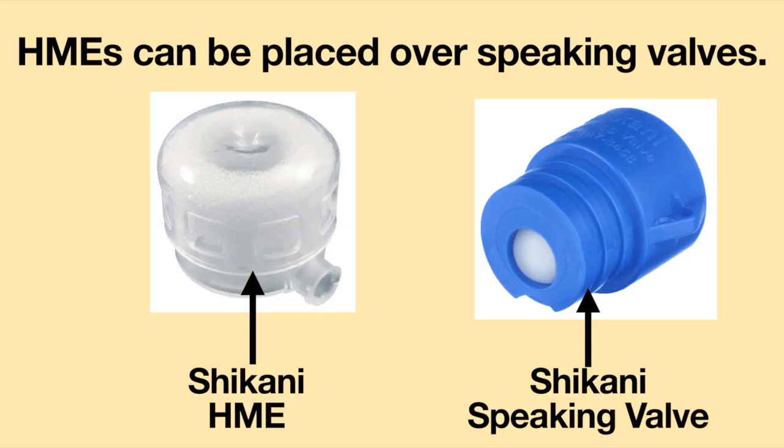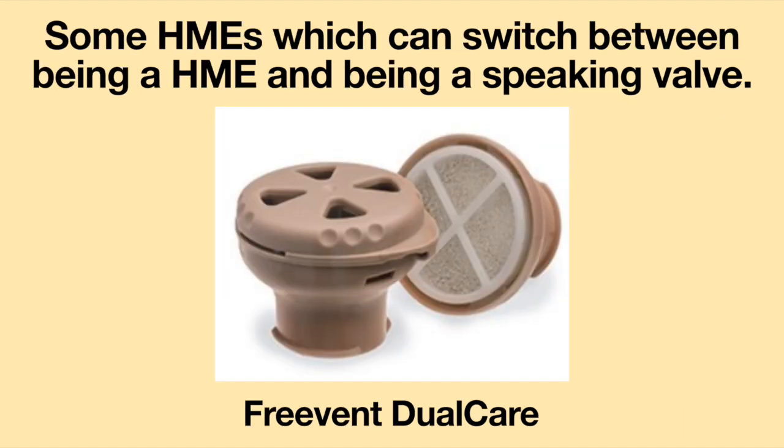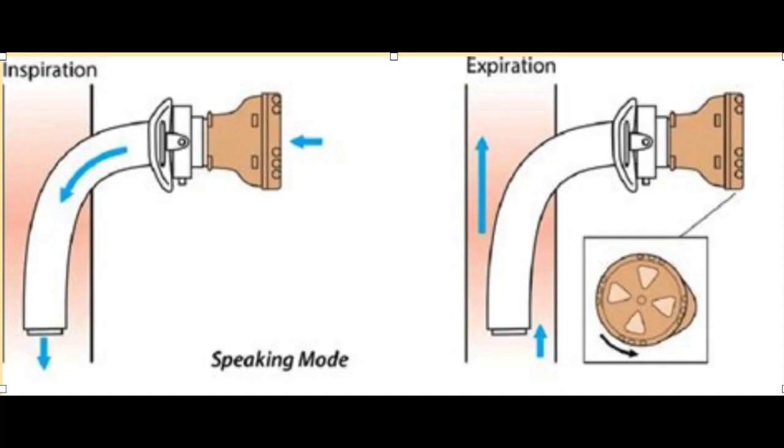One example of an HME attaching to a speaking valve is the Shikani Speaking Valve and Shikani HME. There are also HMEs which can switch between being an HME and being a speaking valve. An example of this is the FreeVent Dual Care. The FreeVent Dual Care is put into speaking mode by twisting the lid of the speaking valve until it clicks into speaking mode position. When breathing out, the air is guided through the vocal cords and out the nose and mouth, allowing for speech to be produced.